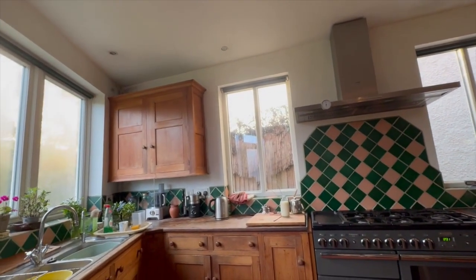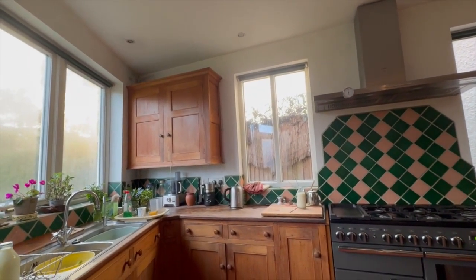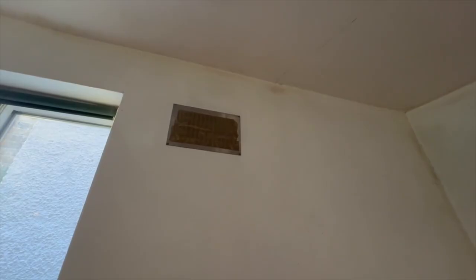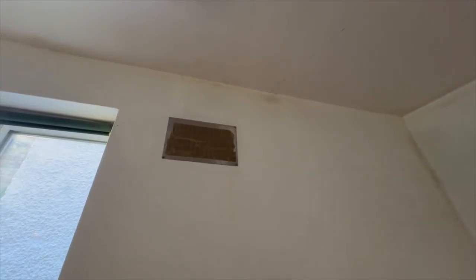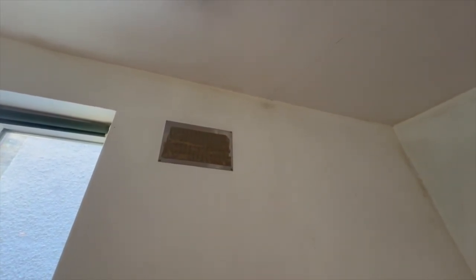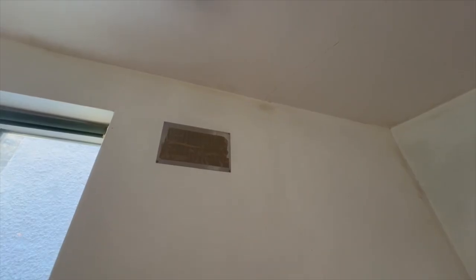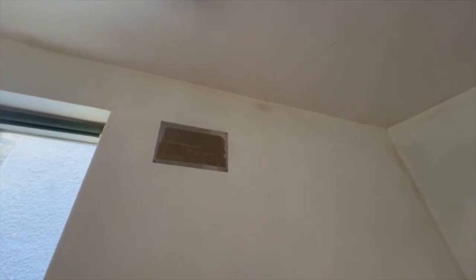Okay. Well, we'll have a look on the outside actually. So, was it a mistake to block that up like that? Well, I'm not a big fan of passive vents, because unless there's air movement on the outside, you're not going to get any of the benefit. But you'll get even less benefit if they're blocked up. Right. It's the worst of both worlds. So you get all the heat loss, but none of the airflow. But you're much better off having an active vent.